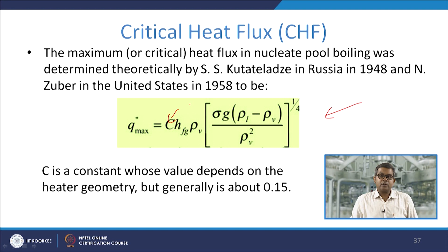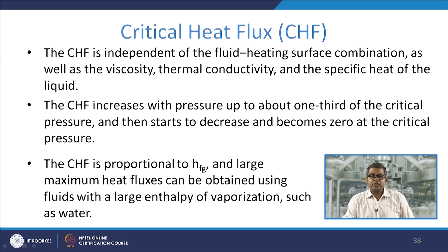Now this CHF, that is the critical heat flux, is independent of the fluid heating surface combination as well as the viscosity, thermal conductivity and the specific heat of the liquid. This CHF increases with the pressure up to about 1/3 of the critical pressure and then starts to decrease and becomes 0 at the critical pressure. The CHF is proportional to hfg and a large maximum heat flux can be obtained using a fluid with a large enthalpy of vaporization such as water.